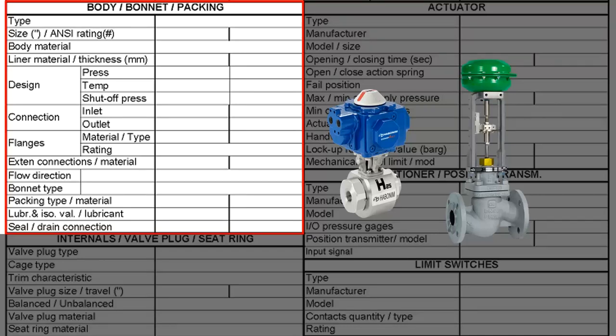I'm just going to talk about flow direction and bonnet type. Flow direction might not seem very important, but in some applications with high dynamic pressure or water hammer possibility, choosing the right direction of flow — being either flow-to-open or flow-to-close — can make a practical difference in actuator sizing or the functionality of the valve. Bonnet common types are bolted, pressure sealed, extended, and simply bonnetless, like the small ball valve shown here.